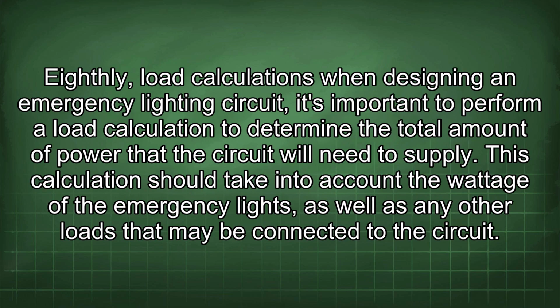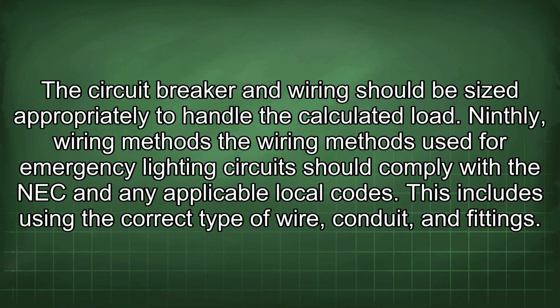Eighthly, load calculations. When designing an emergency lighting circuit, it's important to perform a load calculation to determine the total amount of power that the circuit will need to supply. This calculation should take into account the wattage of the emergency lights, as well as any other loads that may be connected to the circuit. The circuit breaker and wiring should be sized appropriately to handle the calculated load.